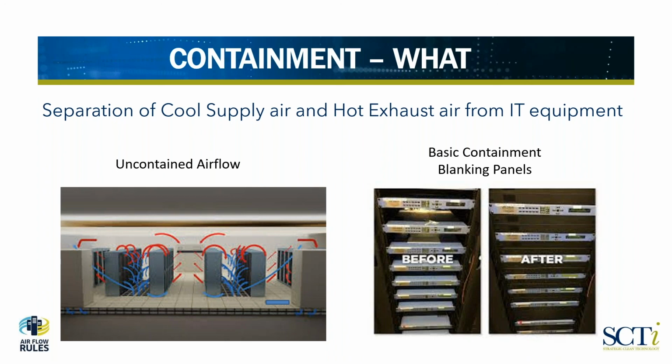Some quite good data centers we've been in, we've seen that percentage of airflow coming up through the perforated tiles relative to what's being supplied as high as 90%. So in those cases, those data center operators have done a really good job of containing the airflow, and it makes a big difference within the data center.